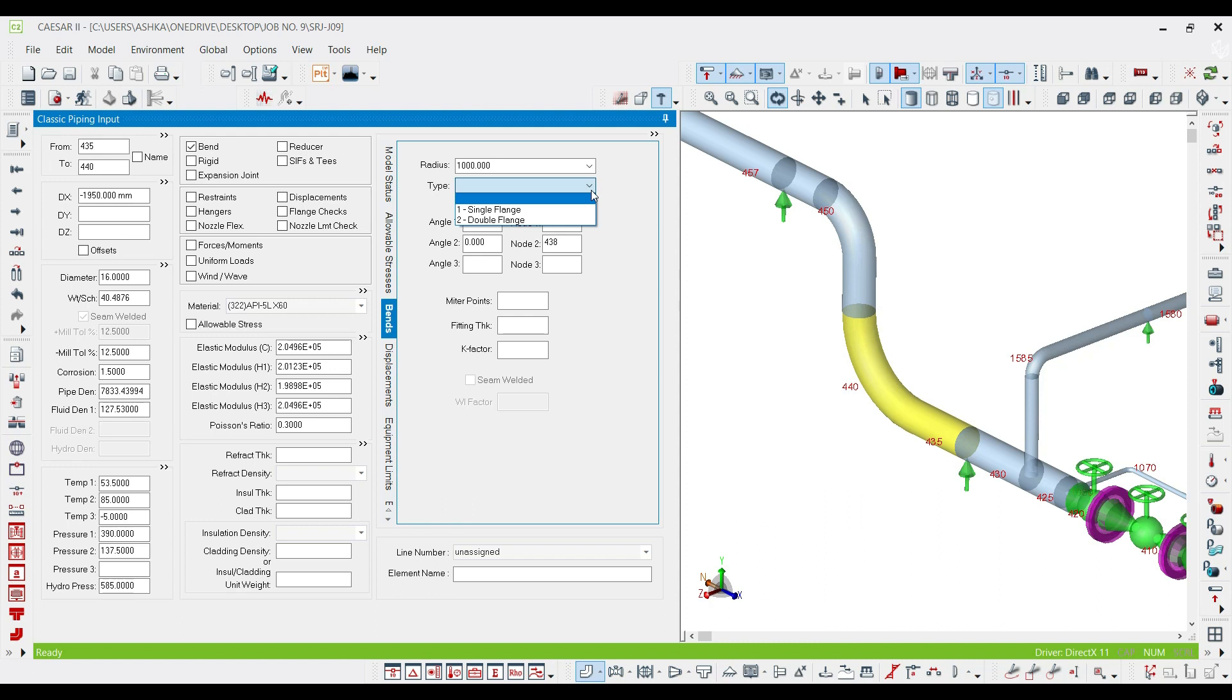If you have a flange or a double flange at a distance less than 2D of the pipe from your elbow, you have to click on this option. It might be because these kinds of solid objects have a big effect on the ovality or flexibility of your elbow, because you know that elbows are a main option for controlling thermal expansion in your piping systems.